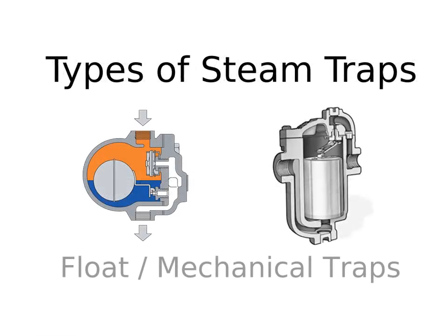There are many different types of steam traps, each designed to work with specific processes. Some are considered float type traps — they work on a similar principle as your toilet. As the float rises when the water reservoir fills, it reaches a certain point and closes the valve to stop water flow. In a float steam trap, the float moves as condensate collects in the reservoir, and when enough has accumulated, it triggers the valve to open and purge, keeping your steam system pure.